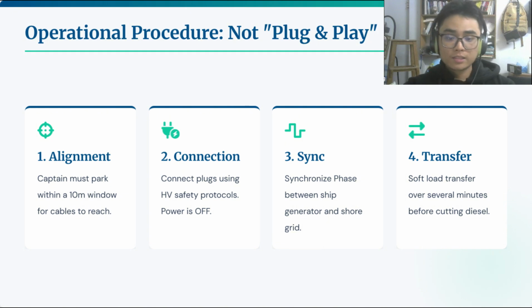Step 3 is synchronization. This is the most dangerous moment. The ship generator is running at 60 Hz, and the shore power is also running at 60 Hz. They must be perfectly synchronized in phase. If the switch is thrown when the waves are slightly out of sync, it can cause an arc flash or an explosion in the switchboard.